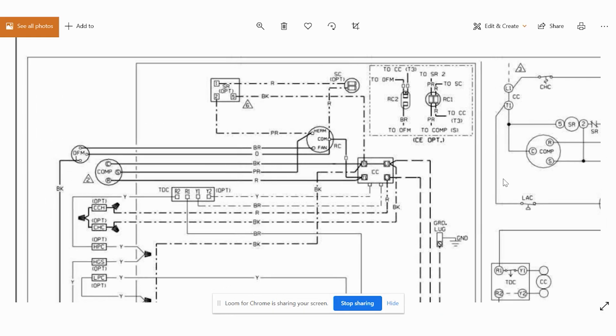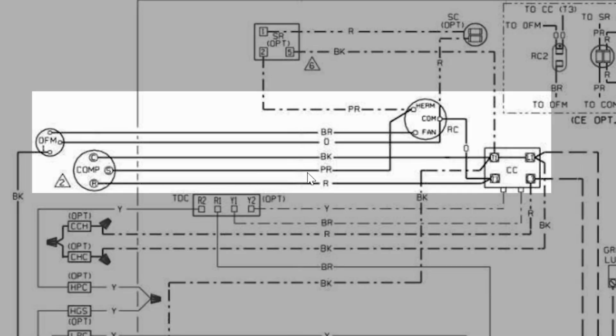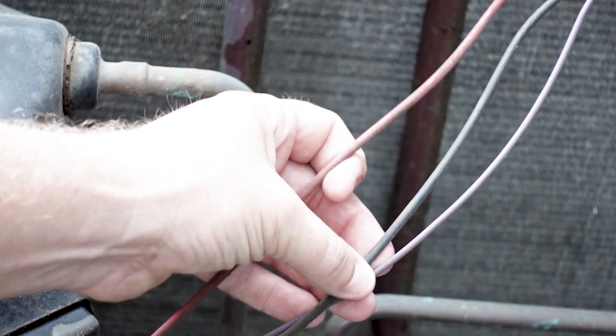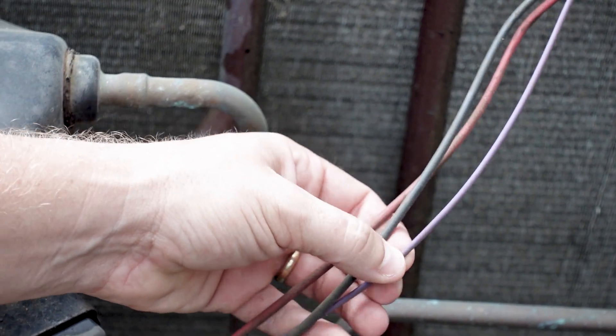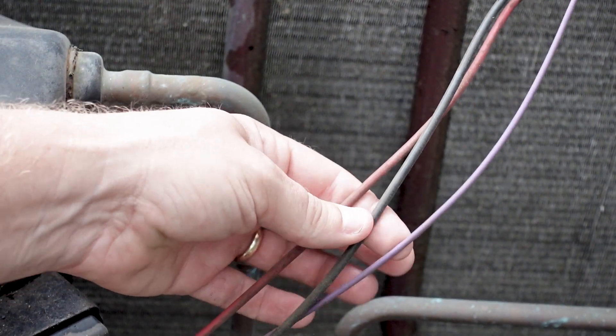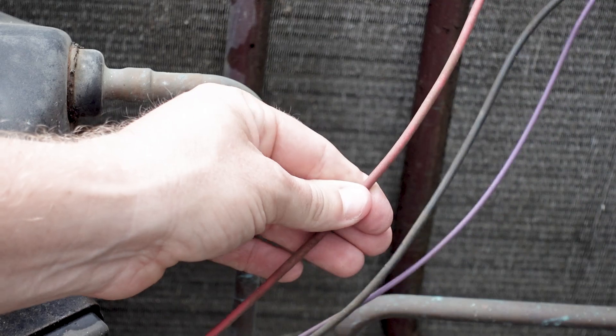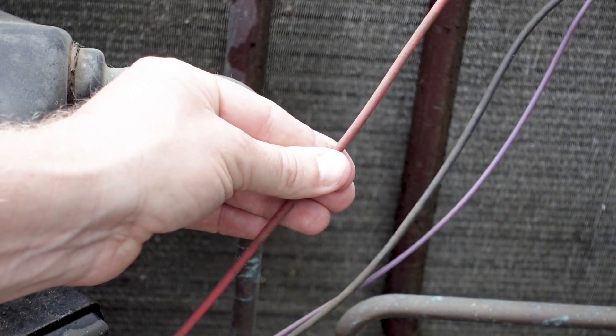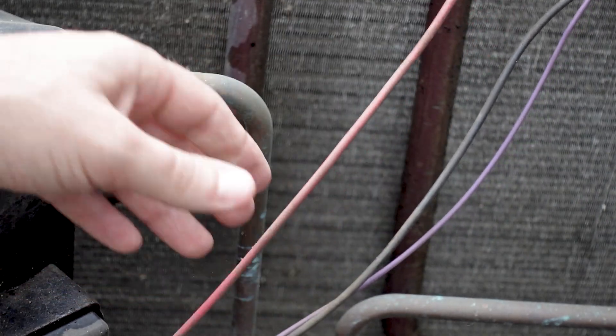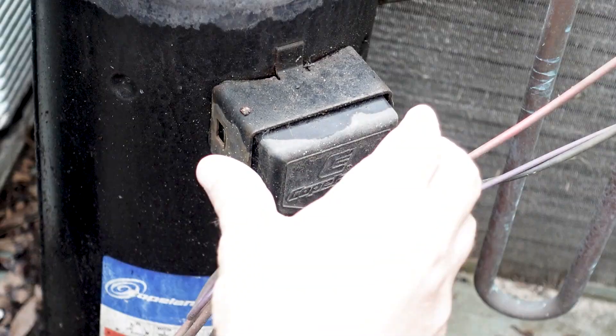If we want to see what color that is, we'd come over here. We'll see that our start is purple. Our run is red going to the run side, and our common is black. Again, we can trace these out from our contactor and we can find our purple, which is our start, our black, which is our common, and our red, which is our run, which comes off of that top run side, what I call the run side of the contactor.